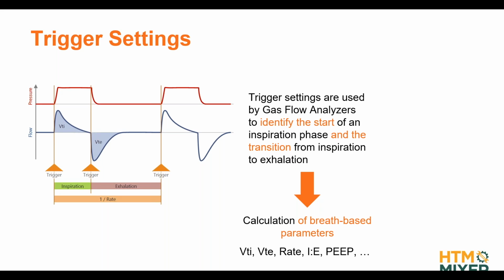So here are typical ventilation waveforms for pressure and flow. And while this ventilation is going on through your gas flow analyzer, it of course can measure flow all the time. But if we want to know what was my inspiratory tidal volume, meaning how much volume went to my patient in the inspiratory phase, and then how much volume came back, for example, or what was the frequency of that ventilation, then somehow our gas flow analyzer needs to know what is an inspiration phase, what is an exhalation phase, and when does the next inspiration phase start? And we do that through trigger settings.